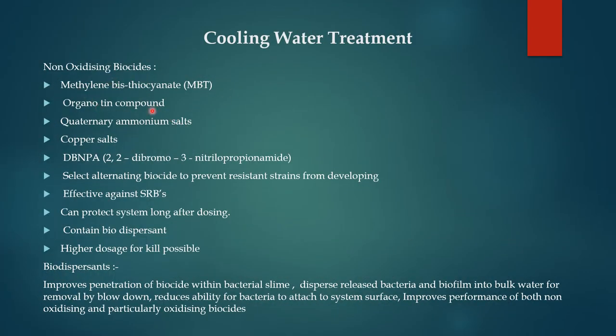Non-oxidizing biocides include: methylene bisthiocyanate (MBT), organotin compounds, quaternary ammonium salts, copper salts, and DBNPA (dibromonitrilopropionamide). It is recommended to select alternating biocides to prevent resistant strains from developing, particularly against sulfur-reducing bacteria. Non-oxidizing biocides can protect the system long after dosing, contain biodispersant properties, and allow higher dosage for kill when required.